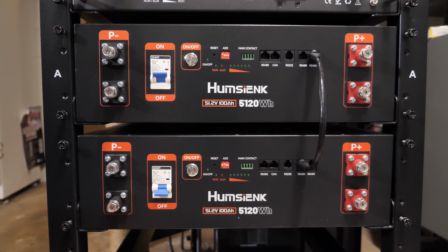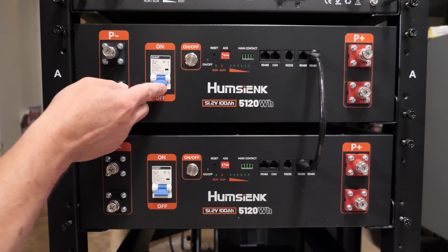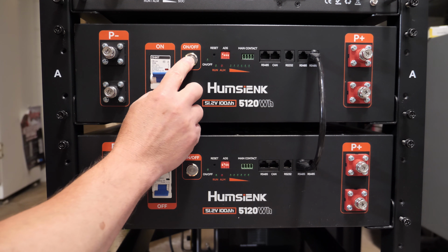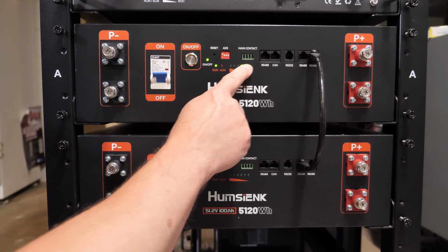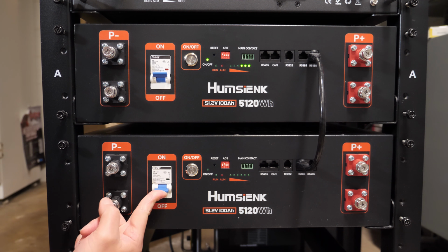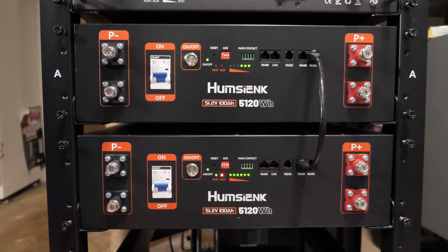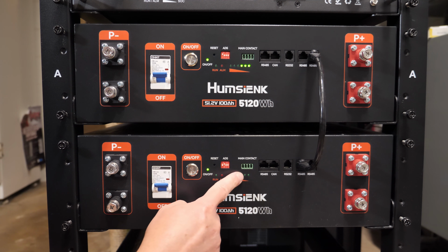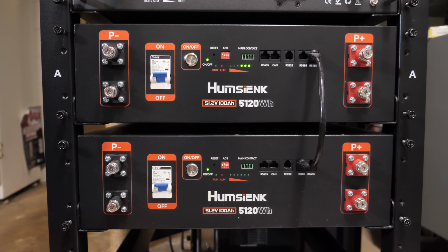After all communication cables are connected, please power on the master battery first, then power on the slave batteries afterwards. So technically, I should be able to turn this one on first, so we will do that, wait for the LEDs to stop blinking, and then we will turn on battery 2 and wait for that to stop blinking. Step 5, once the parallel communication is successful, the slave batteries should synchronize on-off status with the master battery using the master battery's power button.